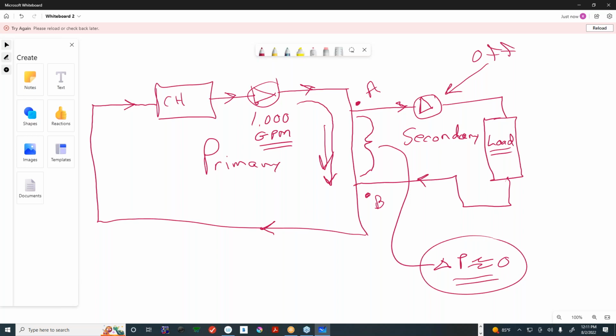Yes, there is a question. I believe it's from one of our good friends at TACO, Mario. Is there a maximum distance separating the two T's for hydraulic separation to operate properly? Well, actually, there is a rough sort of number. Most people will say that that distance should be approximately 10 pipe diameters. So I'll put that in here, 10 pipe diameters. Sometimes we make a diameter circle with a slash line through it. So 10 pipe diameters.